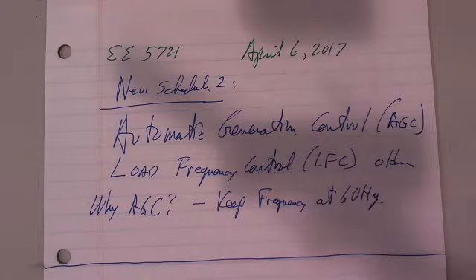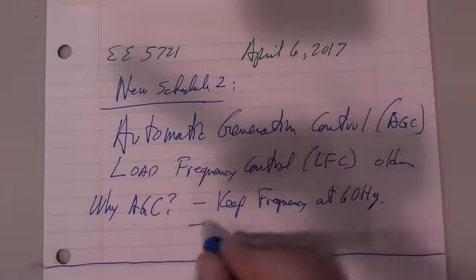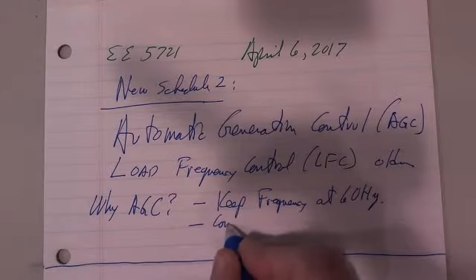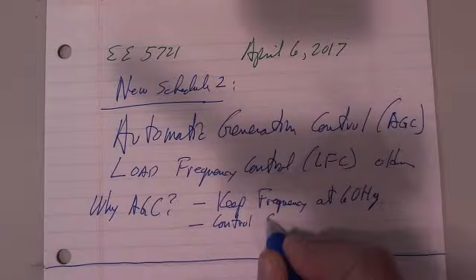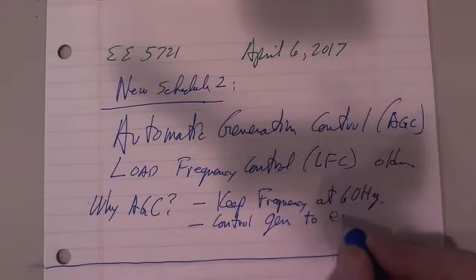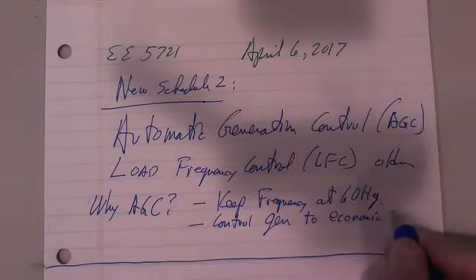In any event, they are the keepers of the time standard, and you can receive that signal in a little clock. And the really neat thing about that little clock is when daylight savings changes and you're supposed to either jump ahead or backward 1 hour, it does it automatically. So that's a very nice feature on those clocks. So you don't really need the grid anymore for time keeping. Nonetheless, you do for the sake of the machinery. Okay. The AGC is to control the generators to their economic set point.